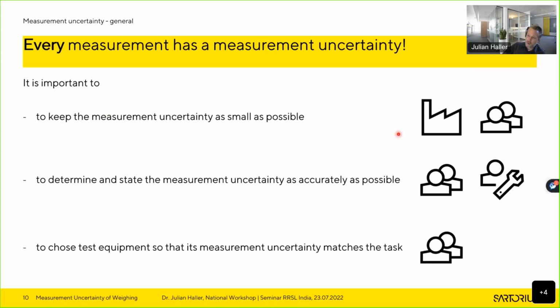And that is, of course, the task on the one hand of the manufacturer of a measuring instrument to manufacture a high quality measuring instrument. But it's also the task of the user to make sure that his process and how he uses the instrument does not increase the measurement uncertainty. So for a weighing instrument, for example, to consider all these, let's say, typical things: to make sure that the balance is leveled, that it is adjusted, that you do not use magnetic probes, whatever. Yeah, so it's the task of the measuring instrument manufacturer, but also of the user.